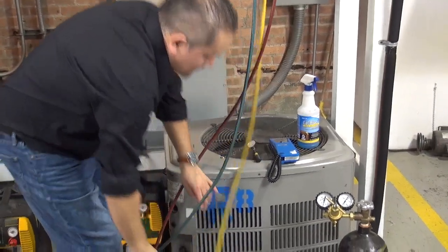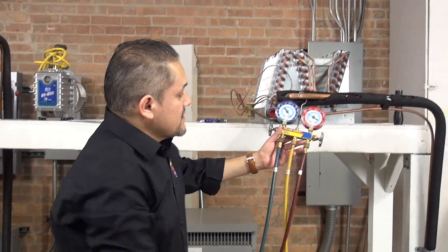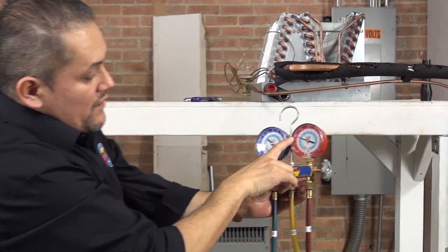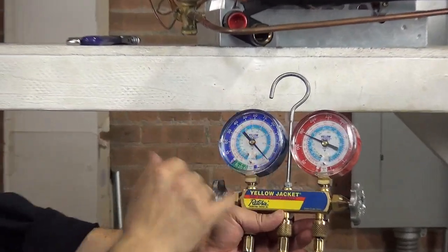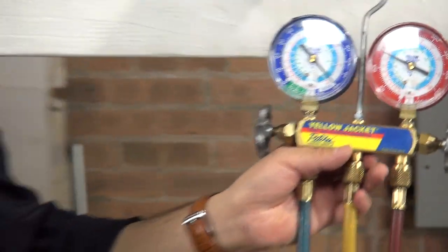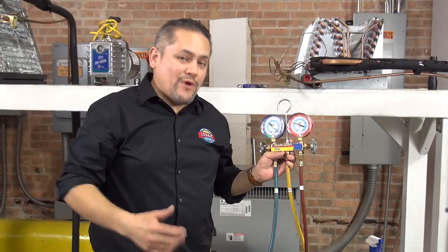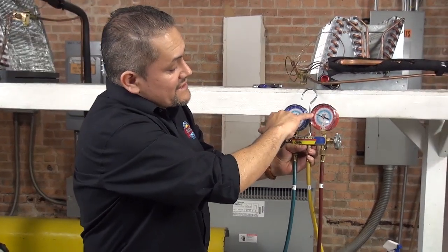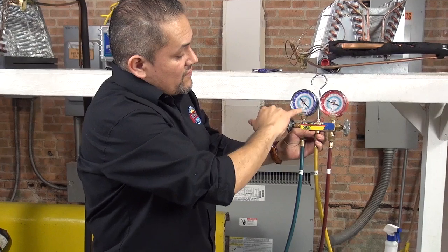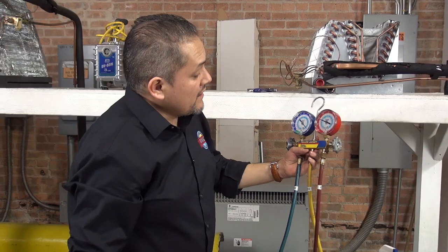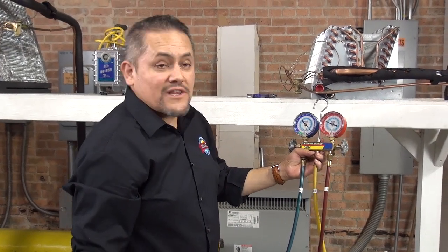And we don't need that no more. We're only going to be using this, and we set the pressure to 150, and this one don't bother because this one goes all the way to 120. So we just set it to 150. Okay? Now, this is where you can actually wait, maybe give it about 20, 30 minutes, and you want to see if this gauge or this one is going to start going back to zero, because remember, we started at zero. And so far, it looks like it's moving a little bit.